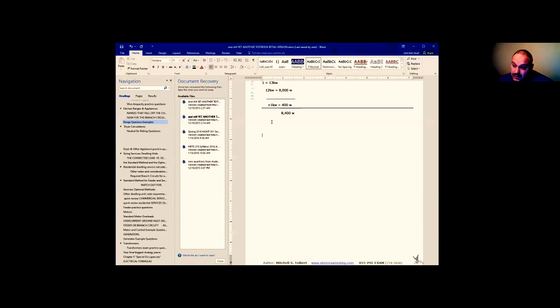With 12? No, but you're close. Remember, you're substituting that 12 for the 8,000, right? So it's 8,000 plus the 2,000. It'll be 10,000. Yep. That 8,000 that you have, you're substituting it for that first 12 kW of the nameplate rating. I know it's kind of confusing. I can say it a million times and it doesn't make it any easier.